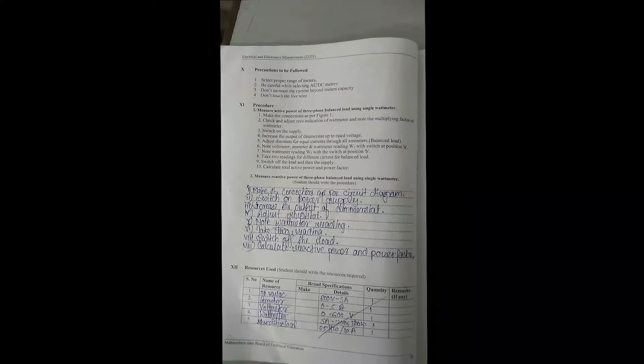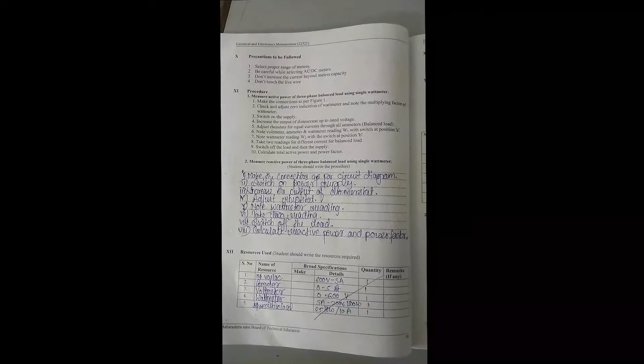Procedure for this practical is: for measurement of active power, first make the connections as per figure. Second, check and adjust zero indication of wattmeter and note the multiplying factor of wattmeter. Third, switch on the supply. Fourth, increase the output of the auto transformer up to rated voltage. Fifth, adjust rheostat for equal currents through all ammeters, that is for balanced load. Sixth, note voltmeter, ammeter and wattmeter reading W1 with switch at position A. Seventh, note wattmeter reading W2 with the switch at position B. Eighth, take two readings of different current for balanced load. Ninth, switch off the load and then the supply. Tenth, calculate total active power and power factor.